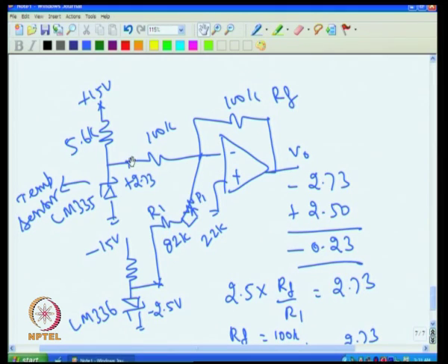So, whatever change takes place goes as it is, with only the polarity inversion. So, the problem comes that if this is not going exactly to 2.73, then there is nothing to adjust. It is essential that when I put it in ice, even though this is not going to 2.73, I have to make it go to 1 volt. Then only our instrument will be correct.